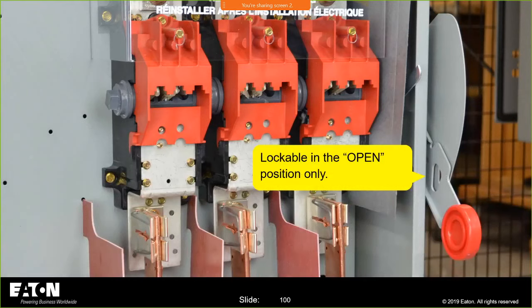So you'll notice in this disconnect switch that you can lock this in the open position, but there's no equivalent hole up here that would make it such that you would lock it in the closed position. So this would meet the requirement of that version of the NEC.